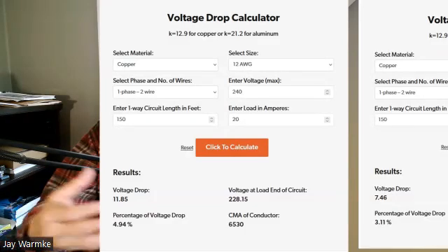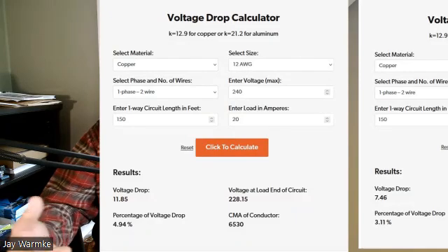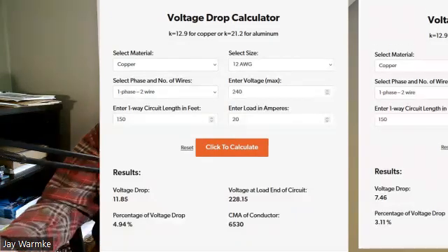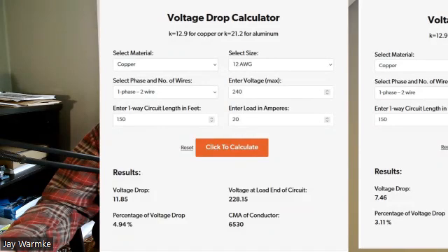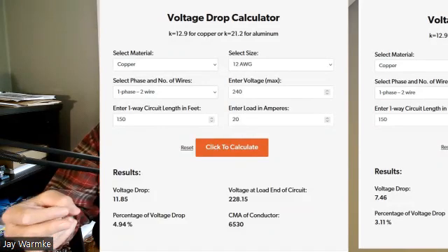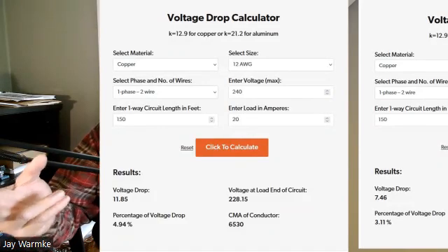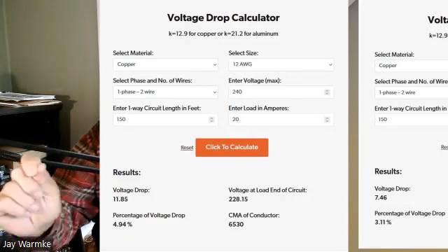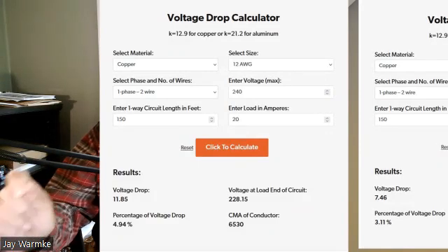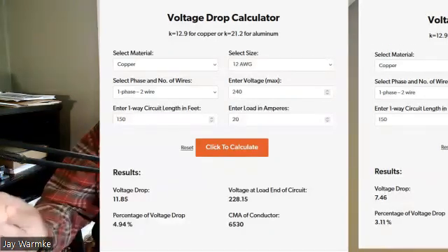240 volt is what we're going to start with. And it's 150 feet. And it's a typical Enphase 20 amp circuit. So this is what I did there. And you'll see that if you look down below, you click to calculate, and it's telling me I'm going to lose 11.85 volts over that particular run.